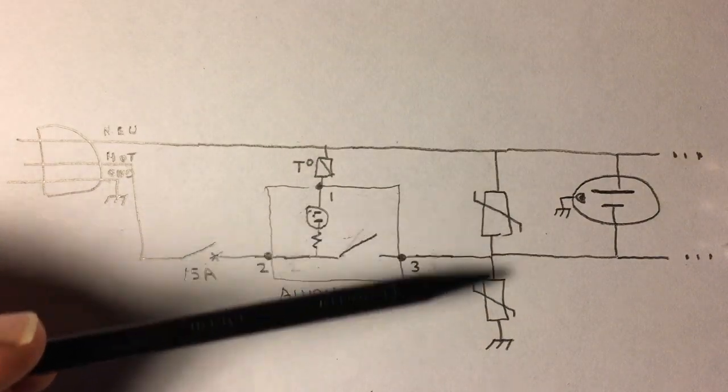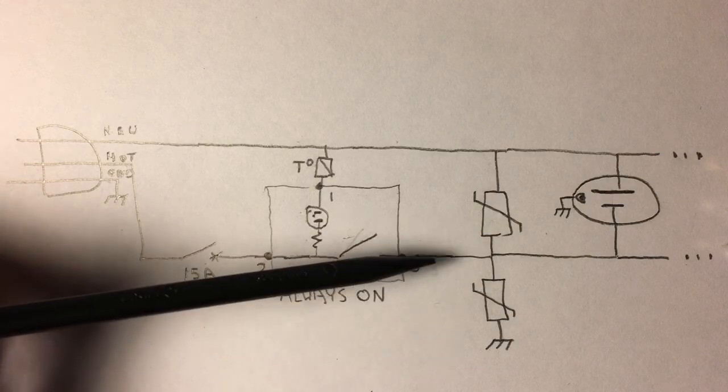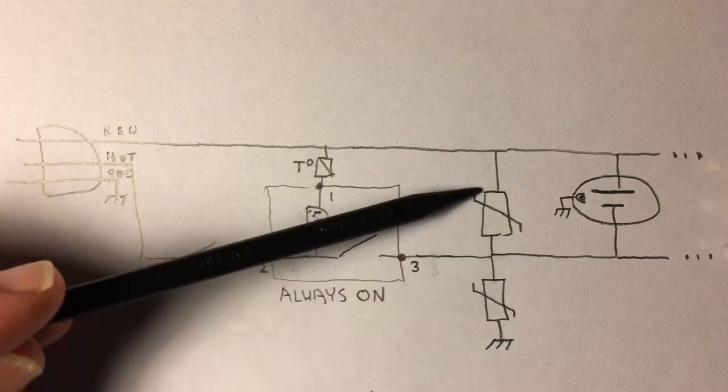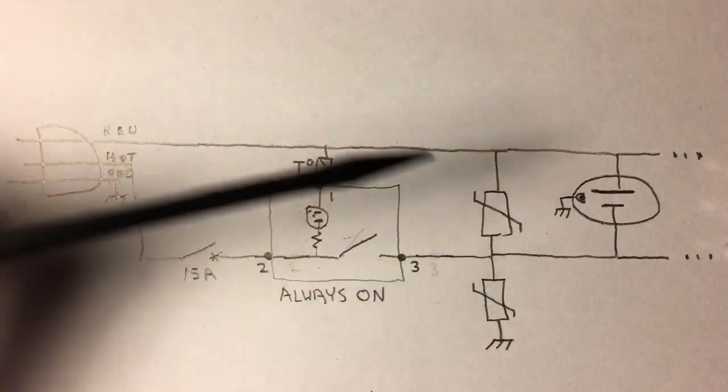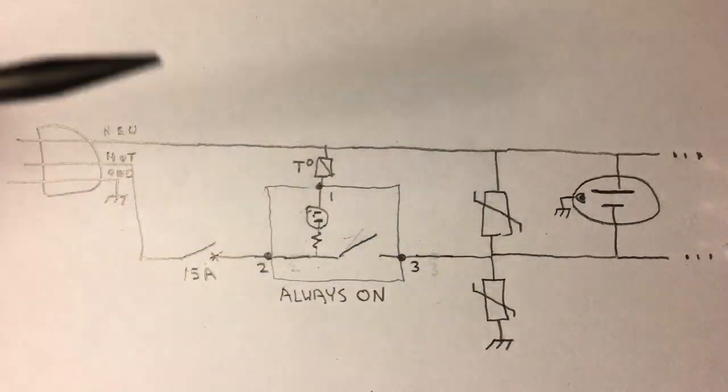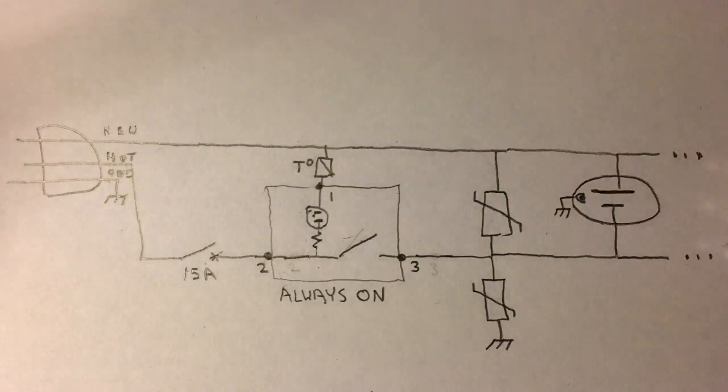Every time one of these MOVs takes a power hit, its breakdown voltage comes down. So these are only at like 200 volts. So they're already pretty low by modern standards and a few hits will get you close to line voltage and you're not getting much protection there.